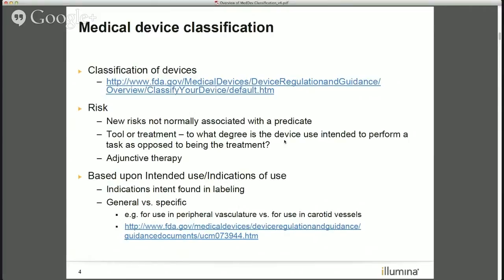Another key factor in determining device class is intended use, which we'll explore later. It's really worth spending a lot of time crafting the language around your intended use. With your initial submission, you'd like to be more general, and as you proceed through development, you get into more specific intended uses in subsequent submissions. For example, a general indication could be 'peripheral vasculature,' whereas down the road you might list specific vessels such as carotid vessels.